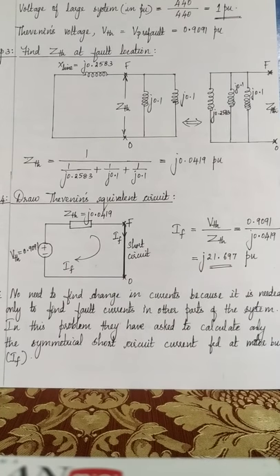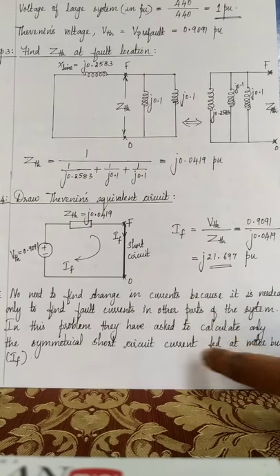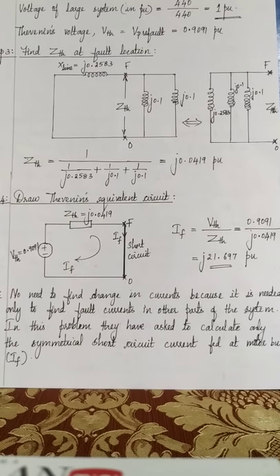But in problems 1 and 2, if you see, they have asked to calculate the fault current at the generator terminal, motor terminal, as well as the fault point. Okay, so that is the reason we are finding IG double dash, IM double dash and IF. But here, they have asked to calculate only the symmetrical short circuit current at the motor bus. So that's why we are stopping at IF. Okay, note down this point.